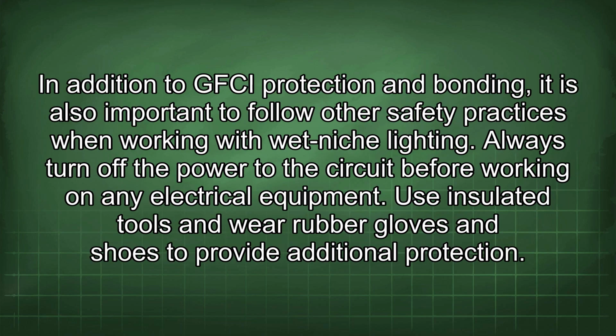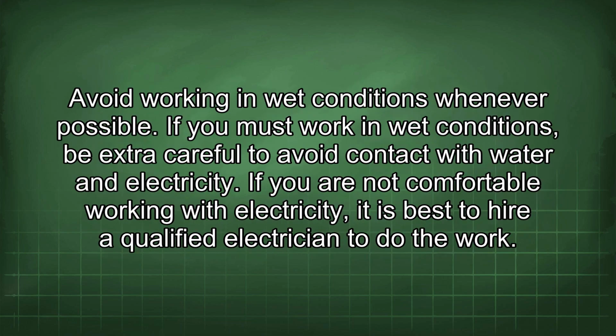In addition to GFCI protection and bonding, it is also important to follow other safety practices when working with wet niche lighting. Always turn off the power to the circuit before working on any electrical equipment. Use insulated tools and wear rubber gloves and shoes to provide additional protection. Avoid working in wet conditions whenever possible. If you must work in wet conditions, be extra careful to avoid contact with water and electricity.